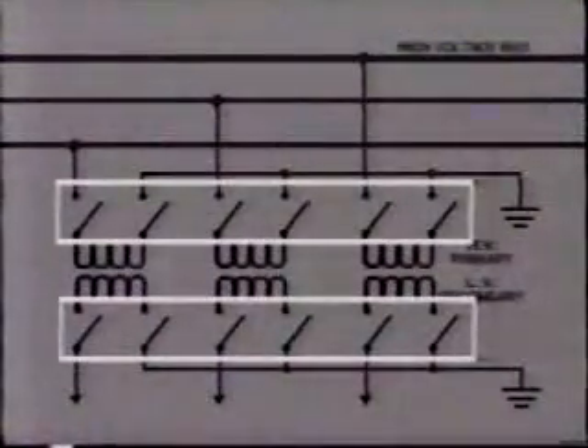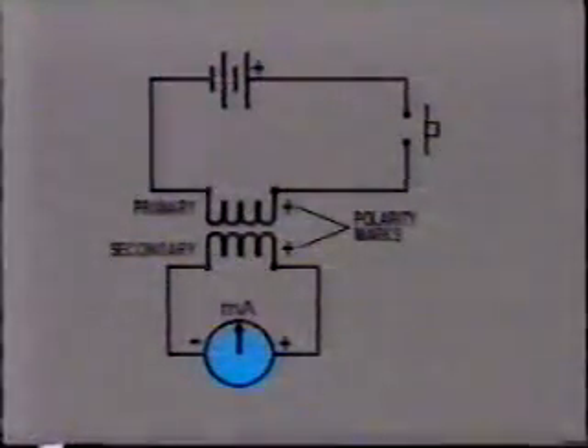During these preliminary tests, it is usually convenient to check the voltage transformers. We need to test that the polarity is correct, and also check the insulation resistance and the turns ratio. Before conducting the tests, both the primary and secondary windings must be isolated from external circuits. The insulation resistance is checked between windings and between each phase and ground. One simple method of checking the polarity is by performing a flick or kick test. Each phase must be checked separately.